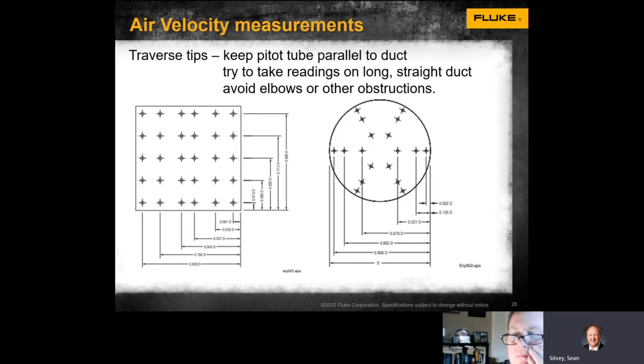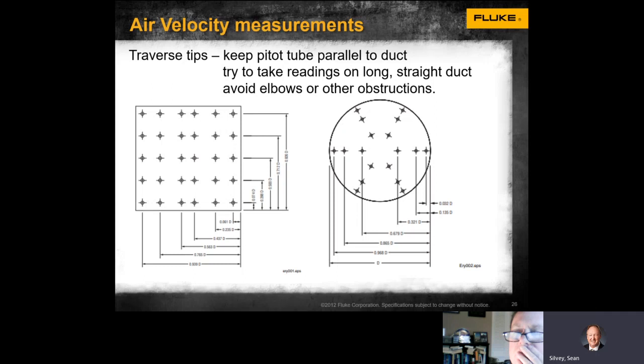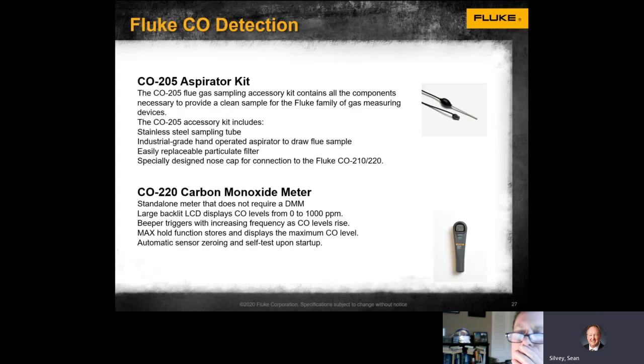Healthcare room pressure applications require a minimum of 0.01, though you'll typically see higher values based on the HVAC system. Air velocity is another key measurement. The kit for the 922 comes with a Pitot tube. When inserting the Pitot tube into a duct, you want to take several traversal measurements to get the true air velocity — whether it's a square duct or a round duct, it's not a one-and-done measurement.